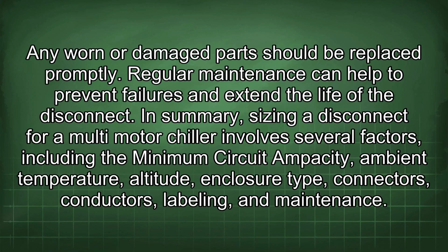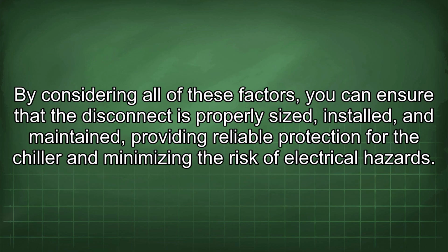In summary, sizing a disconnect for a multi-motor chiller involves several factors, including the minimum circuit ampacity, ambient temperature, altitude, enclosure type, connectors, conductors, labeling, and maintenance. By considering all of these factors, you can ensure that the disconnect is properly sized, installed, and maintained, providing reliable protection for the chiller and minimizing the risk of electrical hazards.